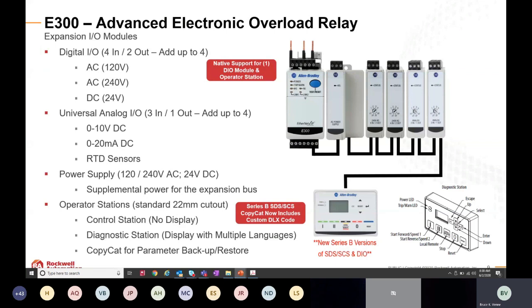And you can add up to 4 digital I/O modules and 4 analog modules. So the digital I/O modules, again, come in the same 3 flavors of different control voltages: 120, 240, and 24 volt DC. And then the analog I/O modules support a wide array of the different analog options that you could bring into these modules. So 0 to 10 volt DC, 0 to 20, 4 to 20, RTD sensors, PTC, things of that nature. Now the E300 will support up to 1 digital I/O expansion module, but beyond that, you would need an additional power supply to really build out. If you're going to do 4 digital modules and 4 analog modules, you're going to need a supplemental power supply to power all those additional modules, because the E300 itself doesn't have enough power to do that.